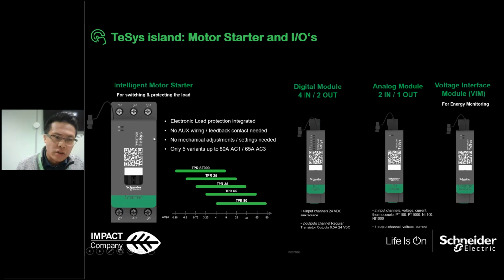So it is a starter. So it is a contactor. Basically the width and the footprint are the same as the TeSys LC1D contactors, and all the accessories, like the bar coupling or all the other accessories, we can use in the TeSys island as well. So the TeSys island inside is an LC1D contactor, but with a PCB board inside. With this PCB board, we can measure the current, gather all the data for the motor and the system, and we can also have overload protection inside the TeSys island.